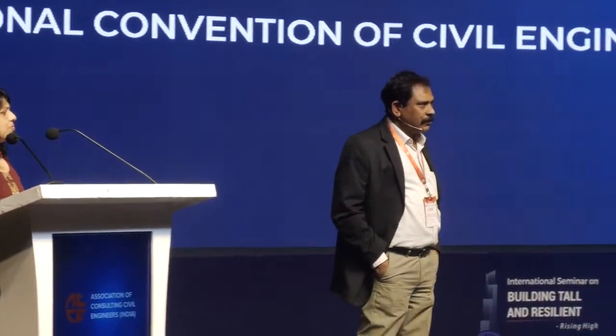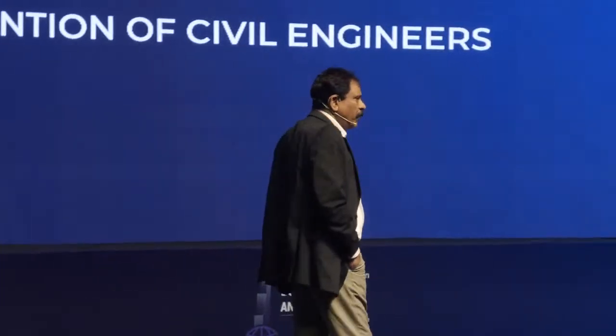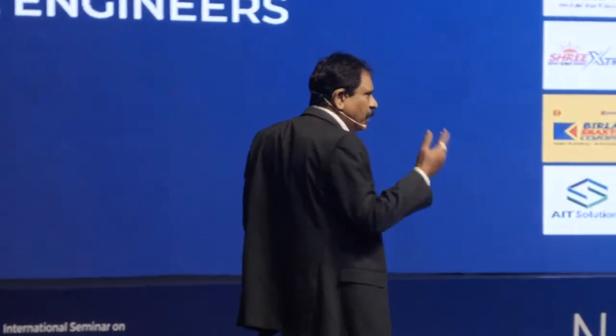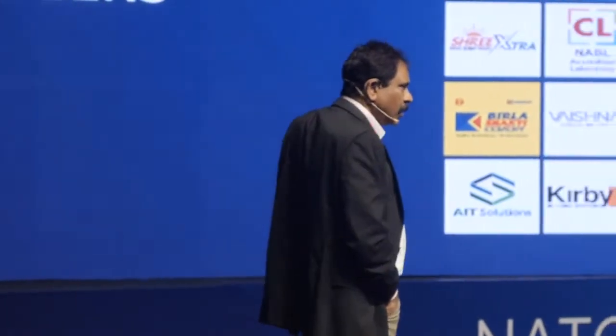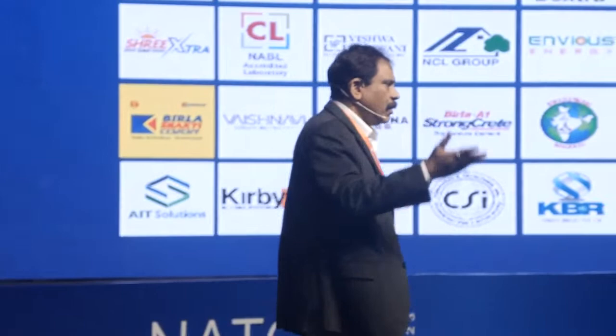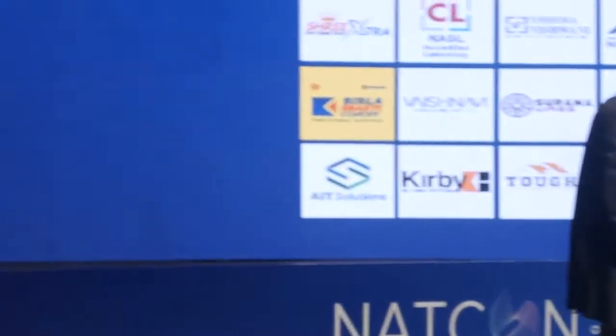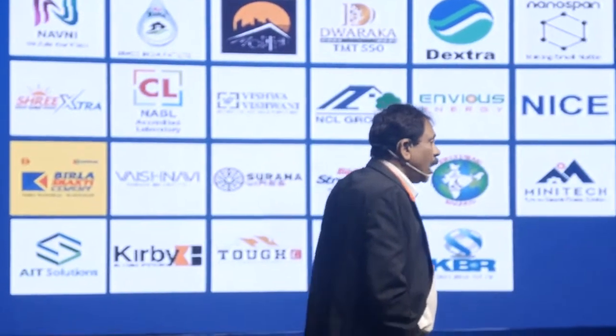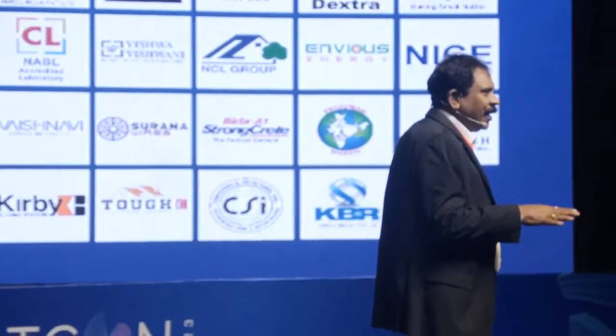Sir, I have one question. No, you can't put any earth pits in the concrete, because there's also a possibility of water oozing out from the basement. You provide an earth pit outside the basement area, beyond that you can provide an earth pit, but the earth pit should be filled with concrete, because concrete has better soil resistivity compared to a lot of other soil. But that doesn't mean all earth pits should be filled with concrete, you can use the building itself for earthing purposes, so you need not have a separate one. Only for testing the earth resistance, if you want a test pit, you can have a pit outside that particular zone.